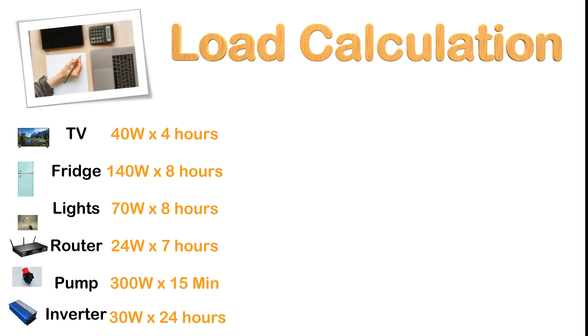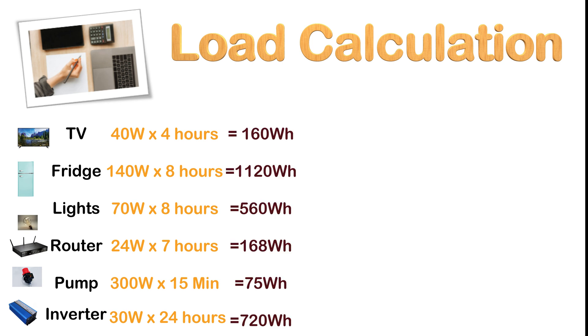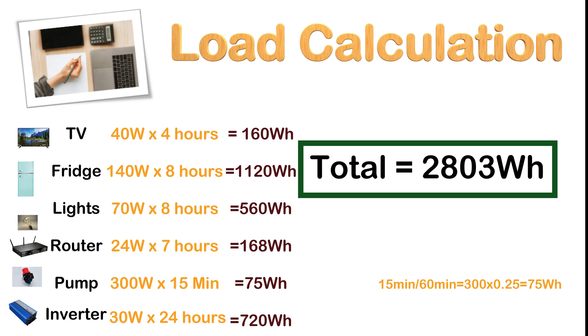Remember, idle consumption can be 10 watts for a 400–500 watt inverter and up to 30 watts for a 4,000–5,000 watt inverter, running approximately 24 hours a day. We then multiply the power consumption by how many hours we run the devices per day. If a device runs for less than an hour — say 15 minutes — divide 15 by 60 to get 0.25 hours. For example, a pump running for 15 minutes: 300 watts × 0.25 hours = 75 watt-hours. We then add up the total, which comes to 2,803 watt-hours.